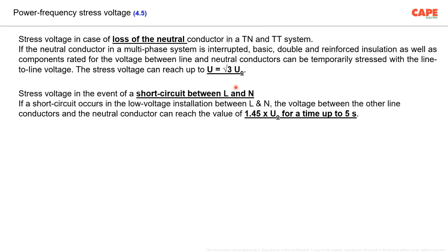The third issue is stress voltage in the event of a short circuit between line and neutral. In the low voltage wiring, once there is a fault between line and neutral, the voltage between the other line conductors and the neutral conductor can reach up to 1.45 times U0, meaning 230 volt, 1.45 times U0 for up to 5 seconds.